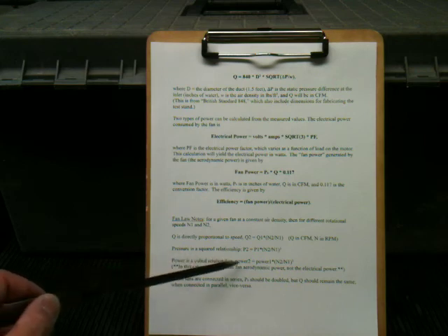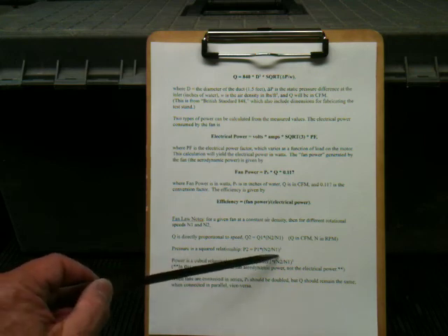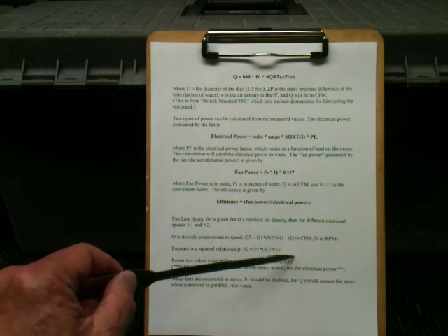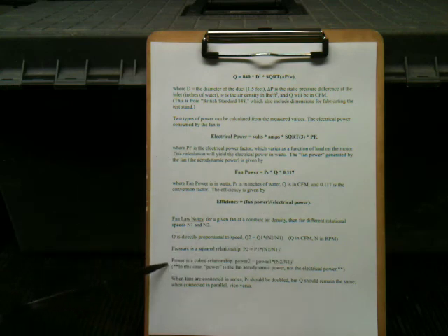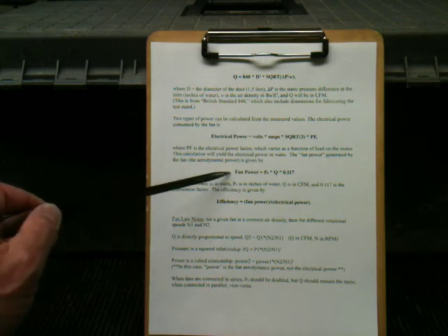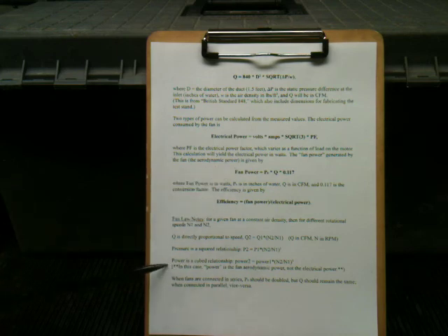So power 2 equals power 1 times the RPM ratio raised to the third power. And in this case, fan power refers to the aerodynamic power that you calculate here and not to the electrical power, okay? So again, you want to see if these laws hold based on the low speed and high speed cases of the 10 horsepower fan and the single 5 horsepower fan.